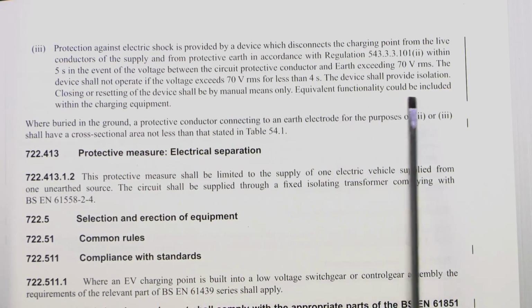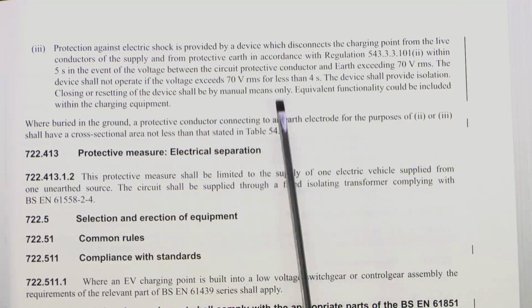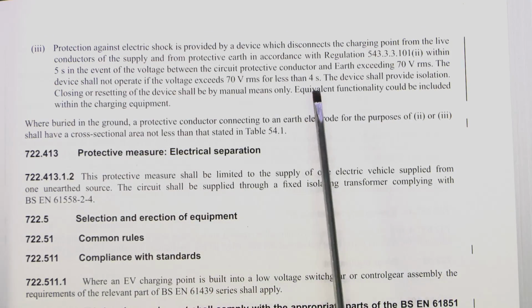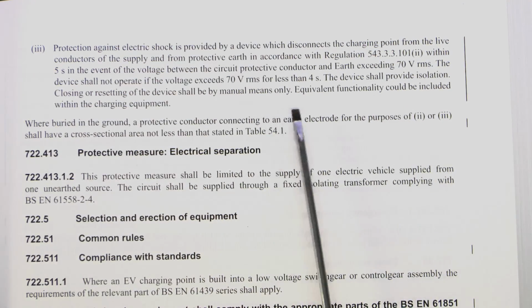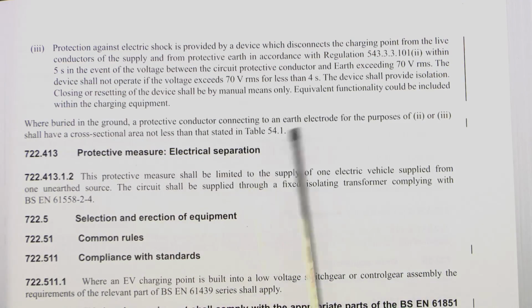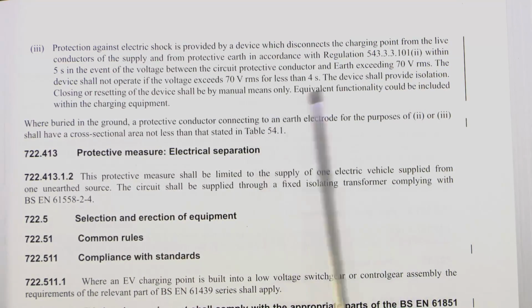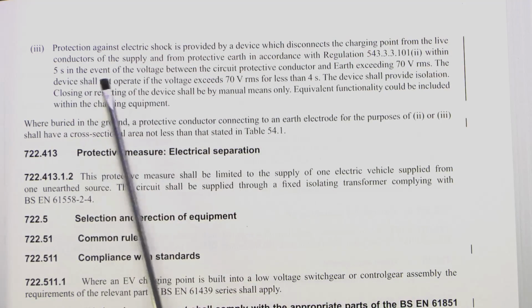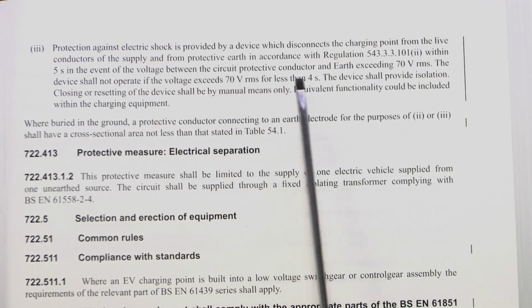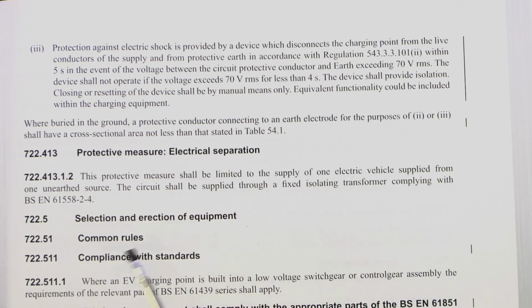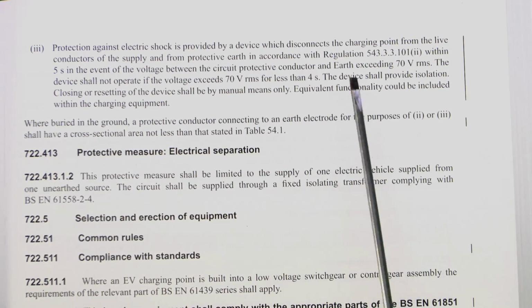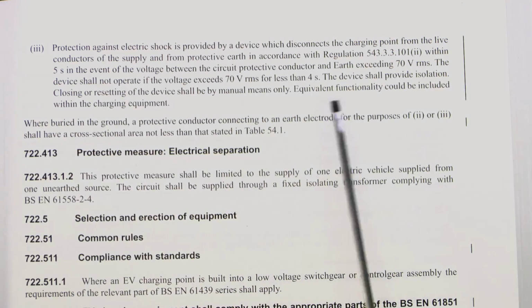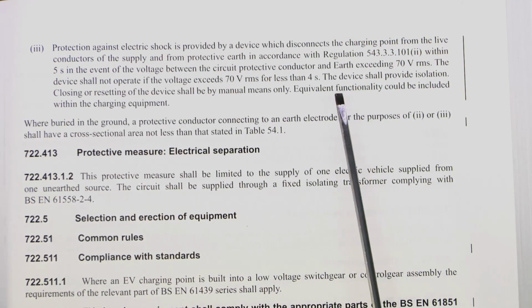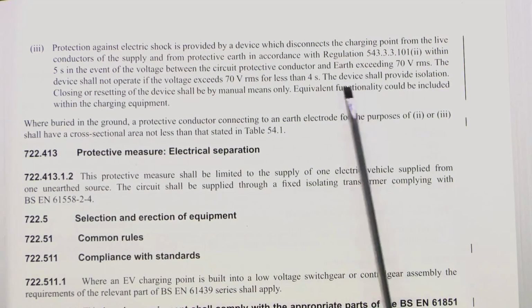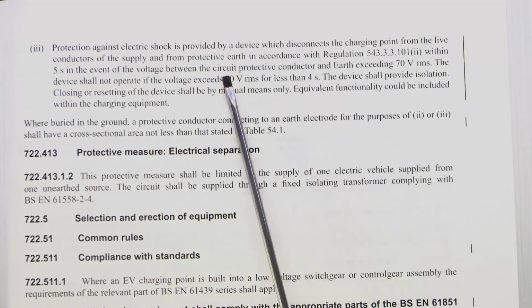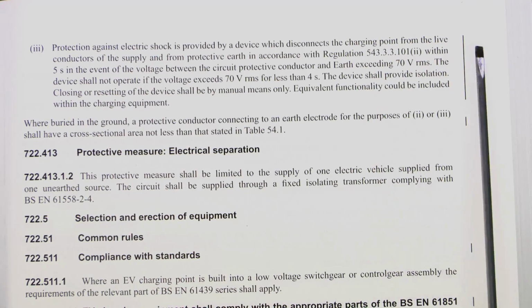It's presumably the intention here that it would be included in the charging equipment, so you're going to buy the actual charging station or the point or whatever, and it would include such a device within that, so that in the event of a break in the PEN conductor, voltage goes up and then it would disconnect that, and crucially it will disconnect, as well as the line and the neutral, the circuit protection conductor as well, because as we've seen in a previous video, which I'll link in here, if the PEN conductor on a TN-C-S supply is broken, then what you essentially get is there's no earth to the installation, and therefore all of the exposed conductive parts or the metalwork of the installation and the earth conductors will go up in voltage to something approaching the full line voltage.